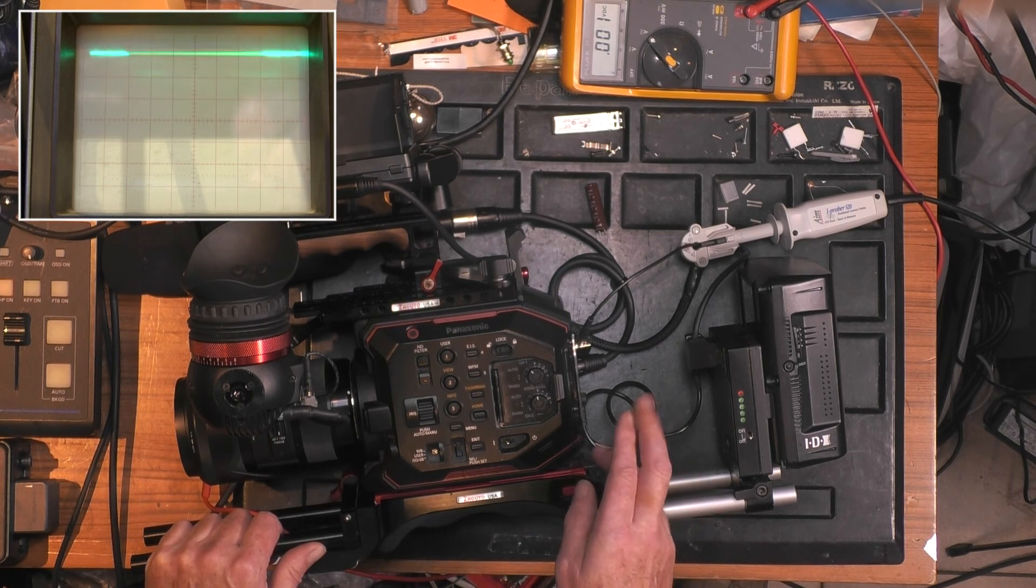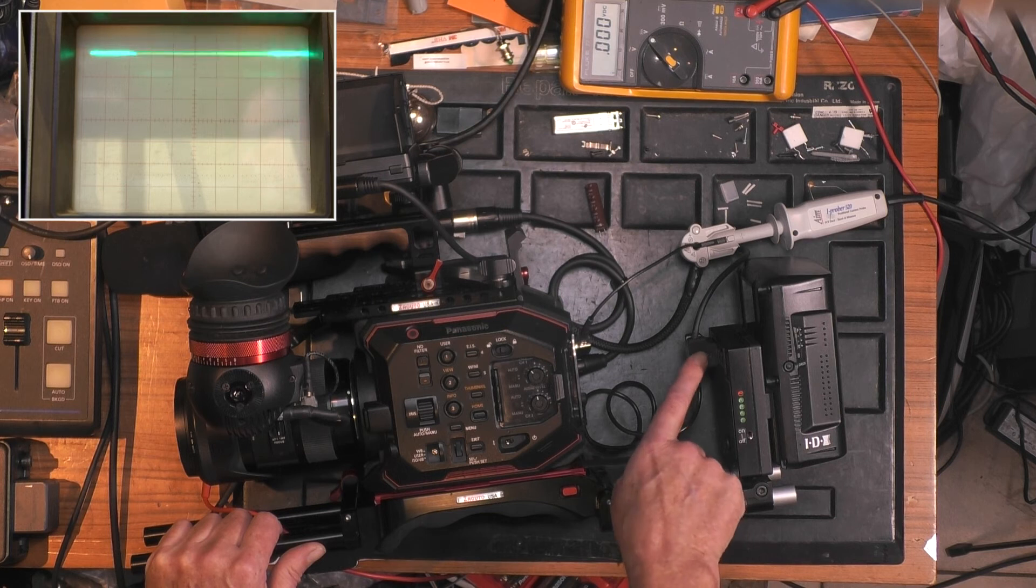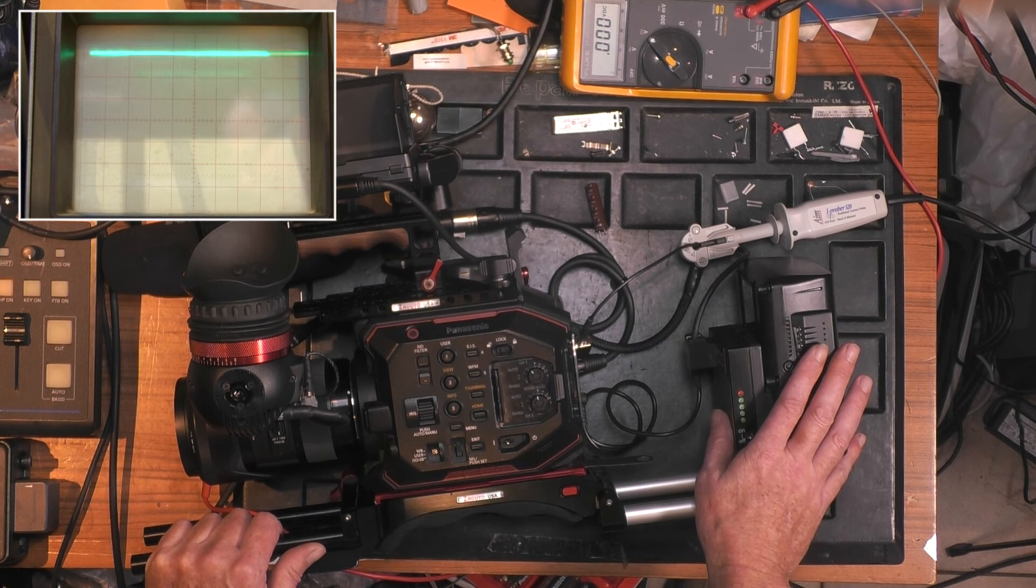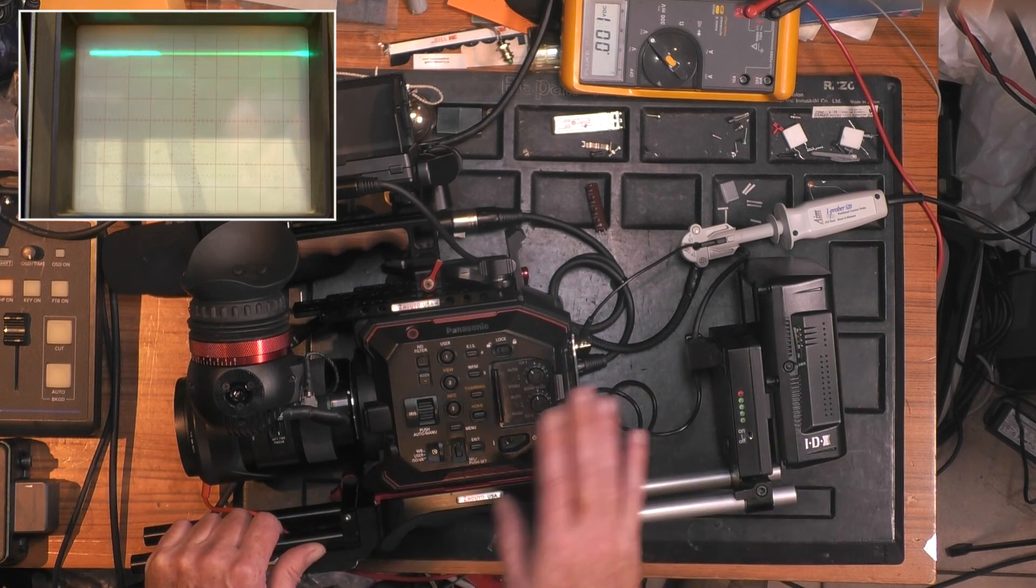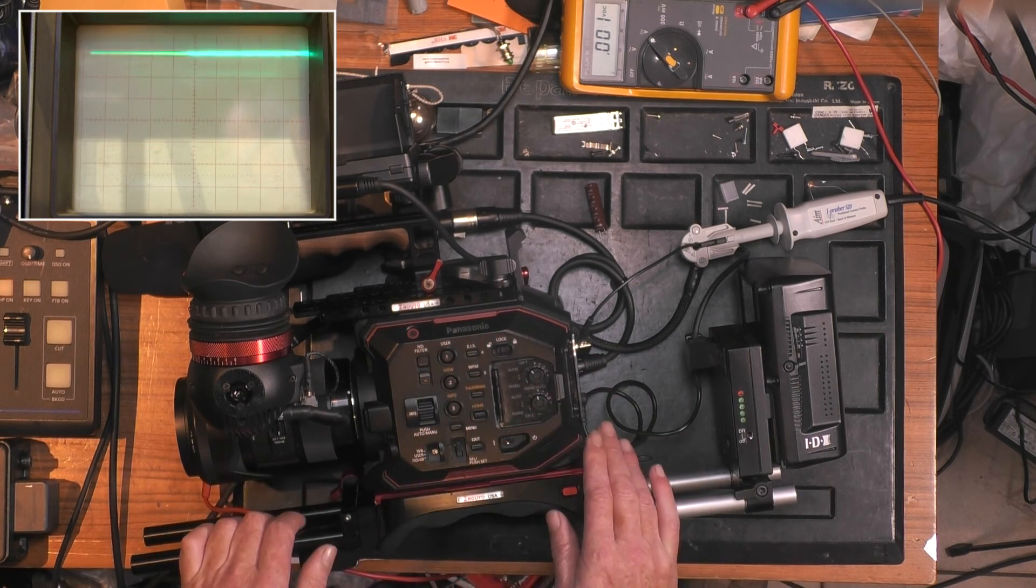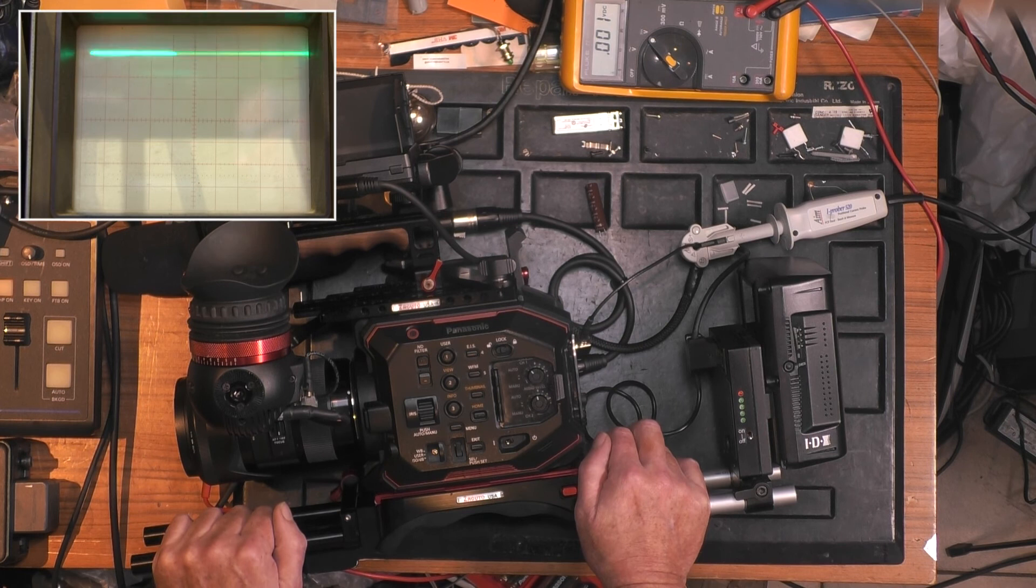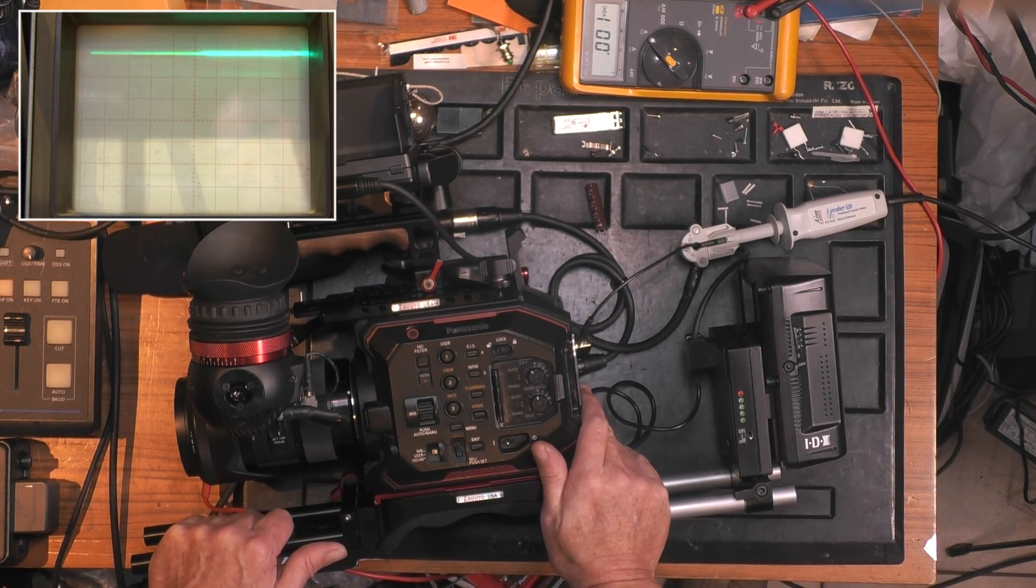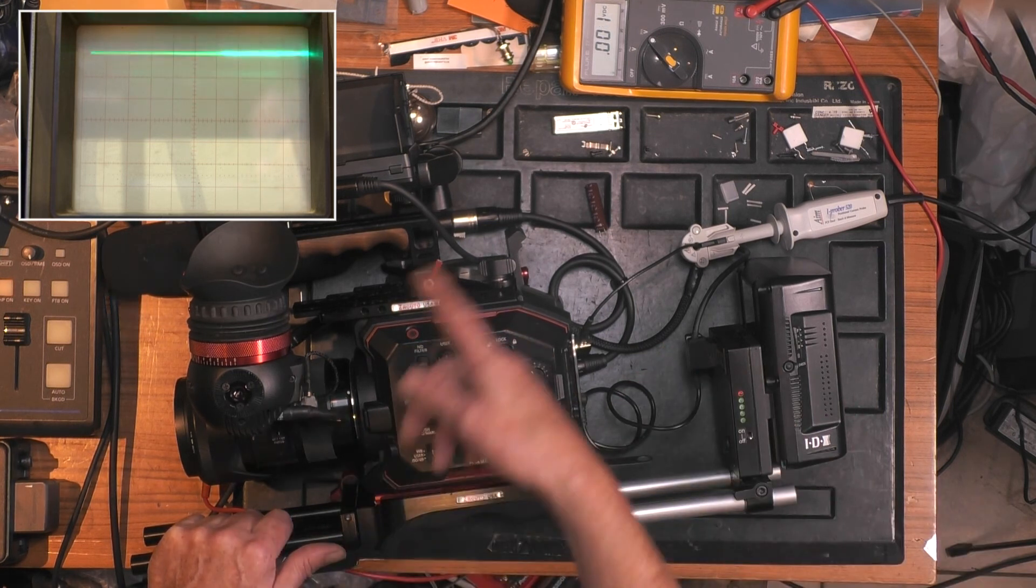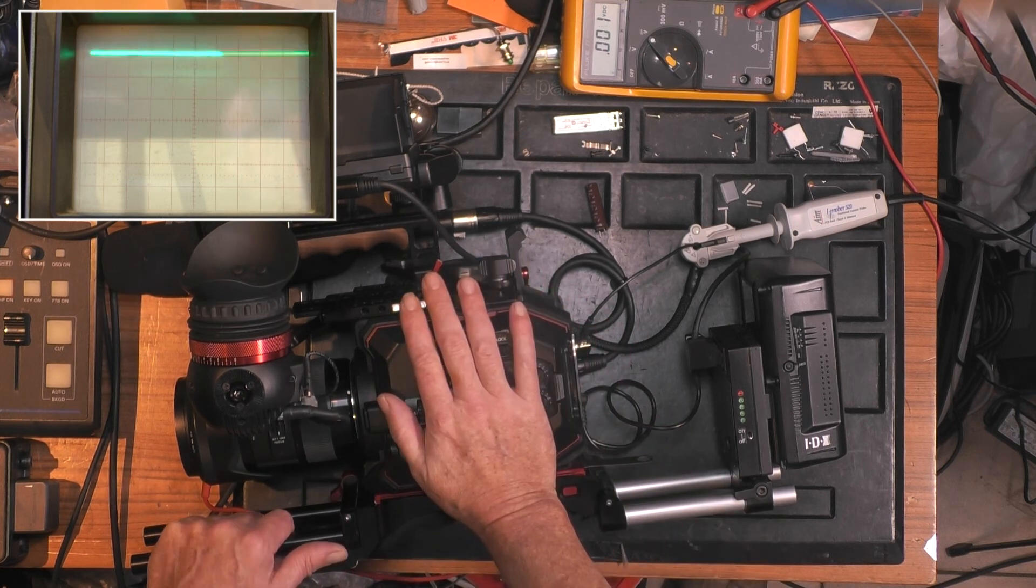But the reason is that they share a common ground. It should work perfectly as long as there is nothing else wrong somewhere in the system, but as soon as something is not working perfectly, the first result is your SDI will be damaged. It can even be by an external equipment that is also connected to this D-Tap and by another connection makes a third loop, and when that is powered on and off, damages this equipment.